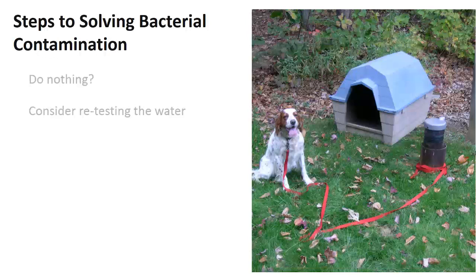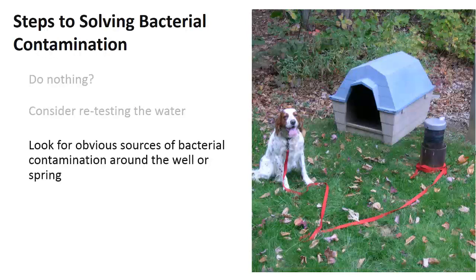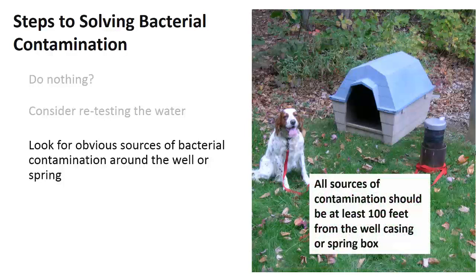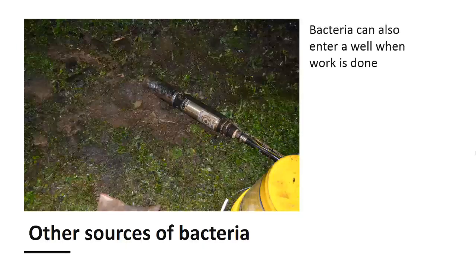Once you are confident in your water test results, the next step for solving the issue is to look for obvious sources of bacterial contamination around your well or spring. In this picture, a dog is tied to the well casing. All sources of contamination such as animals, septic systems, and runoff should be at least 100 feet from the well casing or spring box and preferably downhill. Bacteria can also enter a well when work is done to the well. In this picture, the submersible pump is laying on the yard where it can easily pick up bacteria and contaminate the well when the pump is installed.